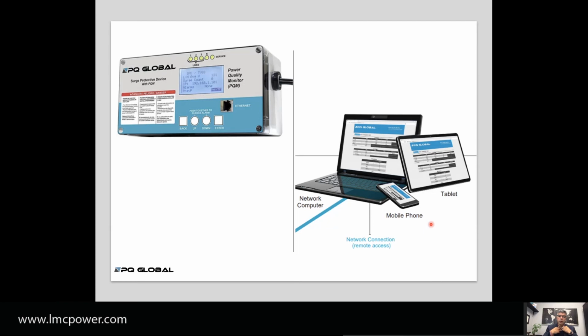Not only are these customers experiencing transients, but a lot of times they can't see it. They don't visualize it. You might install a surge protector and it's continuously protecting them, but they don't know that, or how many times it protected them that day. So what this does is take measurements of how many transients, the duration, the amplitude, giving you credibility. You install this in a panel and go back and say, look how many times this has really protected you throughout this time.